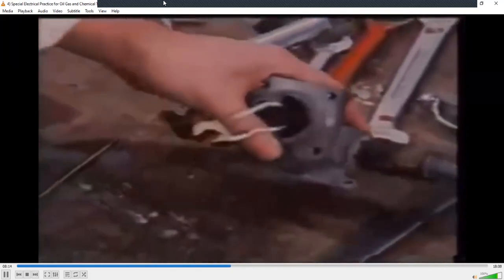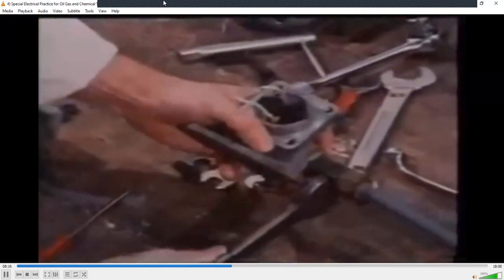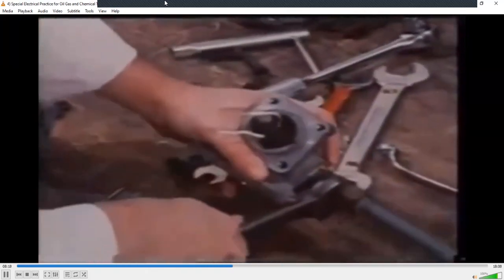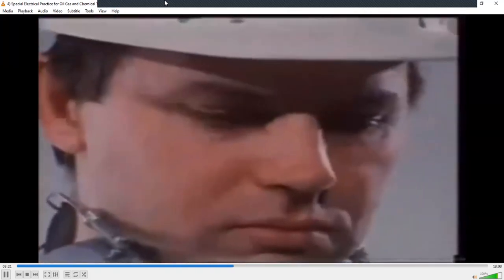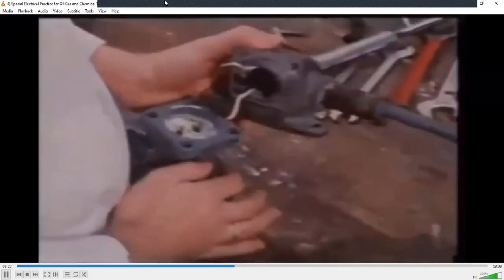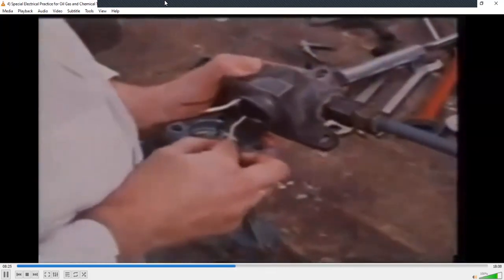The special flame-proof cable gland must be checked for tightness and the electrical connection made. Again, ensuring that the conductor is held tightly in the terminal box. There must be no loose wire strand left in the terminal box. Solder the strands of a multi-strand conductor to eliminate the possibility of short circuit and ensure a secure connection.